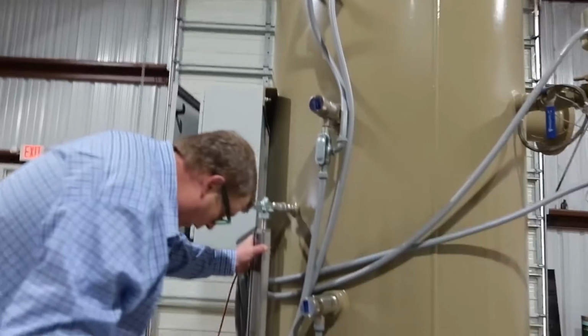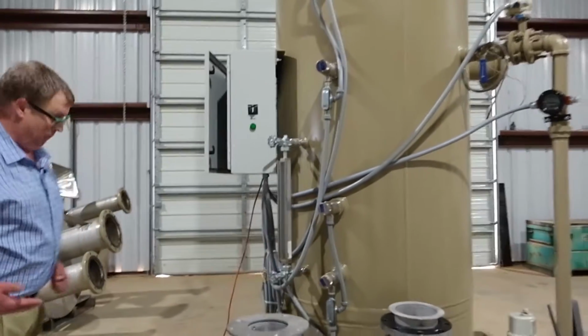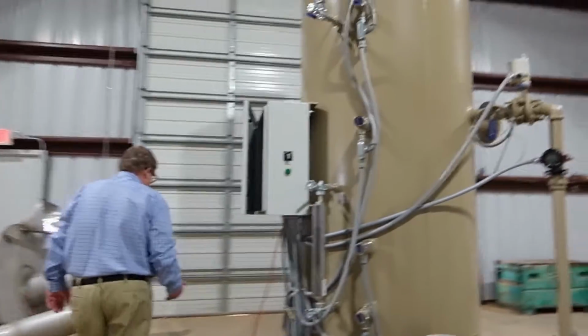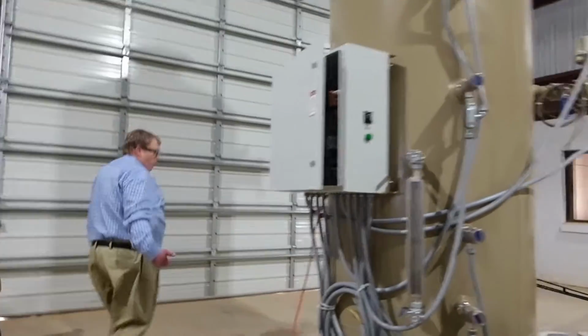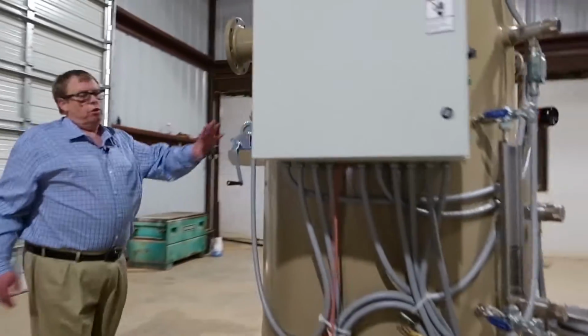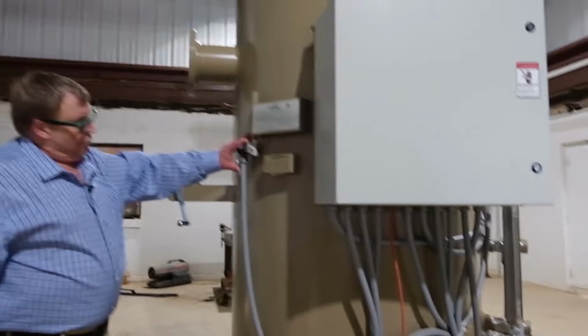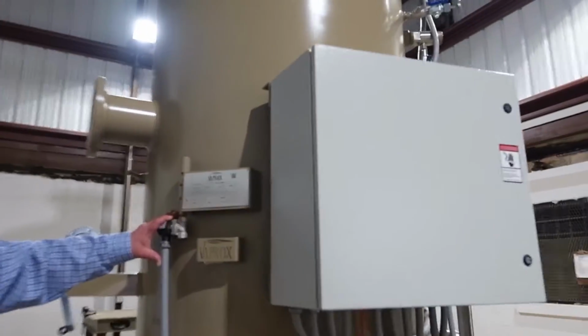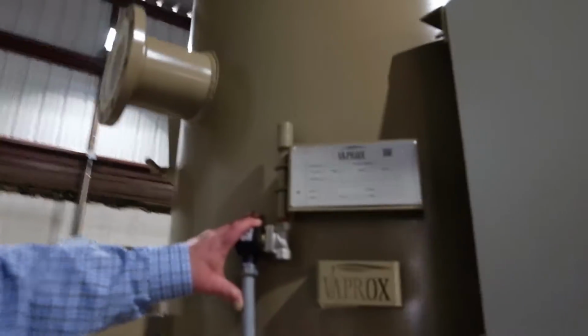On this particular flare, which we've prepared for Apache, Apache's automation group has elected to use a solenoid valve to cut off the supply gas going to the pilot in case a high level switch is actuated.